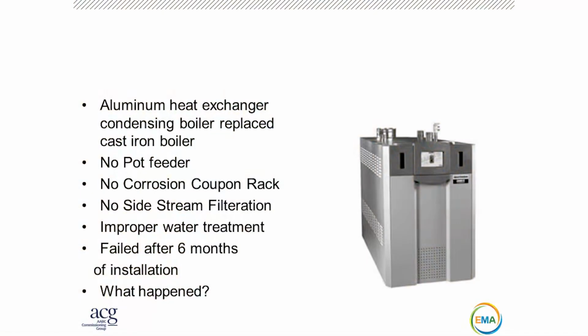So this case study took place in southeast Iowa. The existing boiler was a cast iron boiler. They were going to replace it with a high efficiency condensing boiler, aluminum heat exchanger. Contractor came in, took out the old, put in the new, didn't flush out the system.